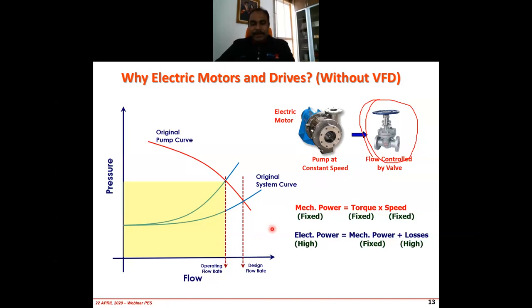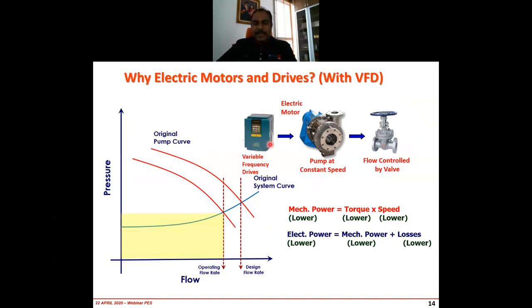Now, instead of that, let's say I connect a variable speed drive or variable frequency drive to this pump system. Same thing: originally, I select the pump curve here and design the operating curve with a certain flow rate. Now, I don't control the mechanical valve. I fully open it. Instead, I control the speed of the pump to control the flow. That means I still work at the lower, reduced flow rate, but by reducing the speed of the pump. When I do that, the pump curve will be shifted, as you can see here.